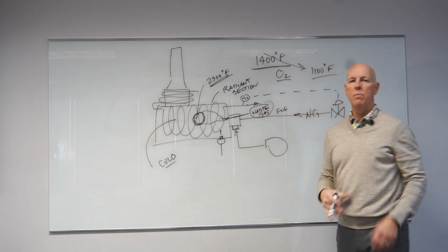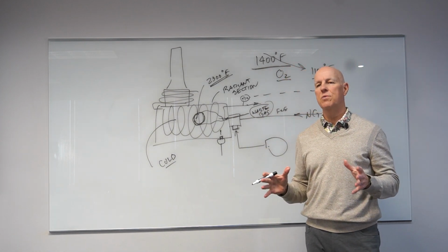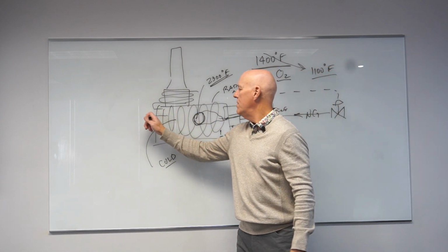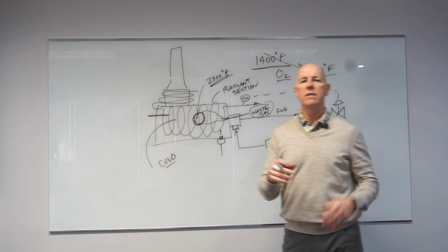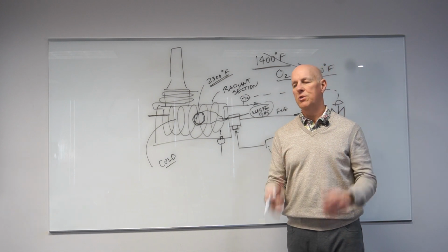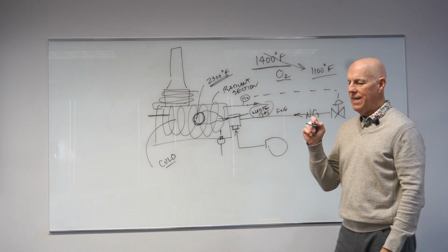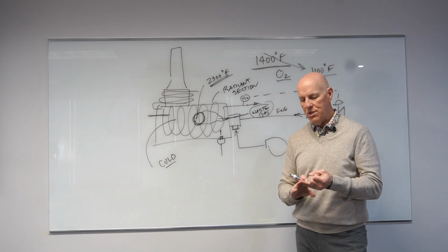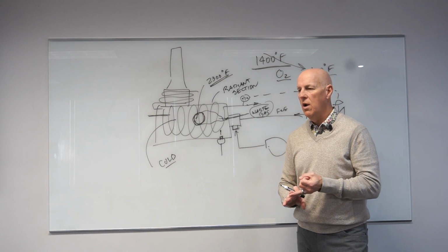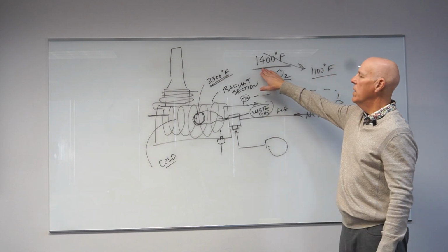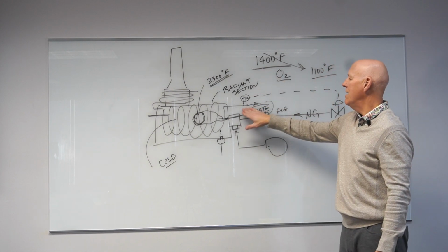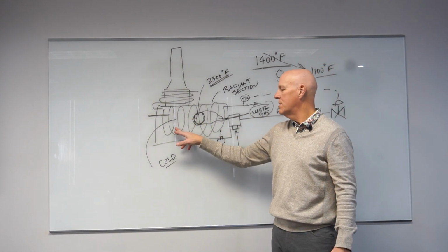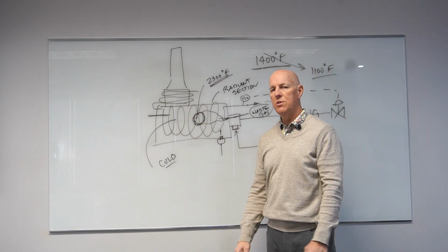If that's the case, then your option is to take this to a thermal oxidizer, which controls based on the flue gas temperature and not a process fluid temperature. So in summary, we can do waste gas in a heater. You have to ask yourself, as the user, are there going to be times where we don't need high firing rates, I don't achieve a flue gas temperature in this box, and therefore I can't get good destruction.